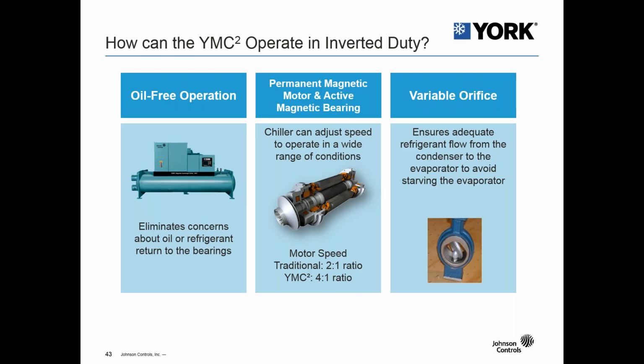So how can the YMC squared chiller operate in an inverted duty or inverted manner? As we walked through in the presentation already, the oil-free operation, having the magnetic bearings, completely eliminates the concerns about oil or refrigerant return to the bearings. We don't have to worry about system pressure differential or having a pump or oil migration to make sure that the bearings are properly lubricated.